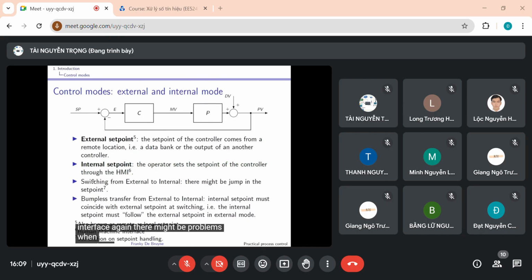Again, there might be problems when switching from one mode to another, so for instance from external set point mode to internal set point mode. We have to organize a bumpless transfer from external to internal set point. So when you're in external set point mode, the internal set point must follow the external set point, so that when we go to internal mode, well, the internal set point coincides with the last external set point. There might also be problems when switching from internal set point mode to external set point mode, for instance in a cascade. When in internal mode, the external set point should be chosen appropriately, and this will be discussed in the section on cascade control.